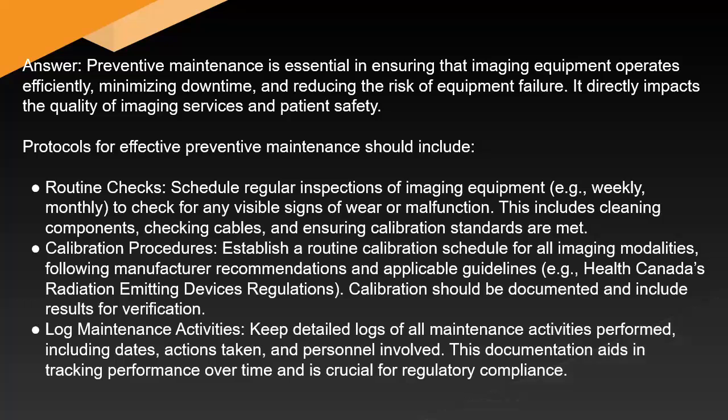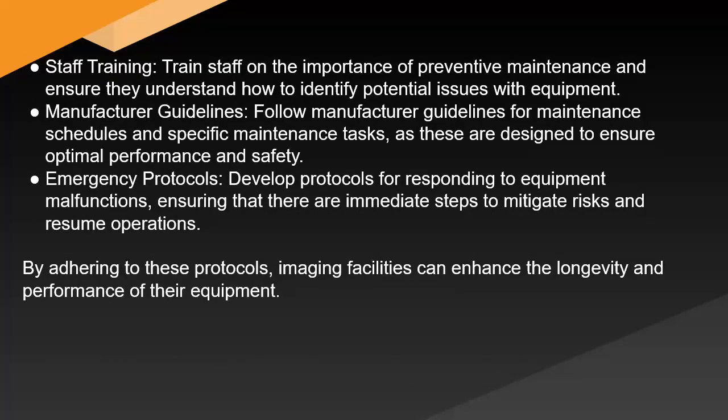radiation emitting devices regulations. Calibration should be documented and include results for verification. Log maintenance activities: keep detailed logs of all maintenance activities performed, including dates, actions taken, and personnel involved. This documentation aids in tracking performance over time and is crucial for regulatory compliance. Staff training: train staff on the importance of preventive maintenance and ensure they understand how to identify potential issues with equipment.